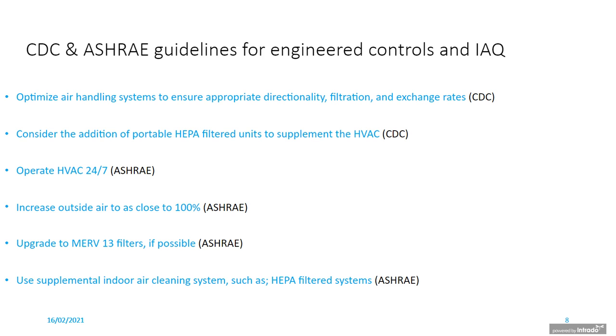So let's go over some of the CDC and ASHRAE guidelines for engineering controls to improve indoor air quality. As we know, it's a concern for many on the call today. As per the CDC, they want to optimize air handling systems to ensure appropriate directional airflow patterns, appropriate filtration integrated into the ventilation system, and appropriate air exchange rates. That's the number of times you have outdoor air coming in and processed out continuously. They also want to consider the addition of portable HEPA-filtered units to supplement the existing HVAC system.